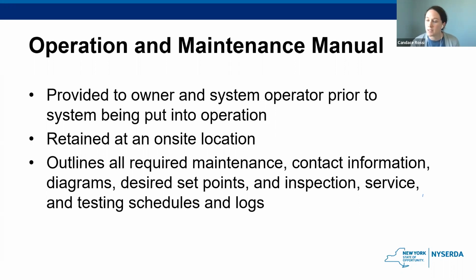So the operation and maintenance manual clearly identifies the required routine maintenance actions, has to include the name, address, and phone number of an agency contracted to service the system. It needs the maintenance and calibration information, including wiring diagrams, control drawings, schematics, system programming instructions, and control sequence descriptions for all of the system's components. It should outline desired control set points, a schedule for inspecting and recalibrating all controls, a service record log, a form that lists the schedule for all required servicing and maintenance actions, and space for logging retained on site. And inspection and testing records shall be maintained in the operation and maintenance manual.